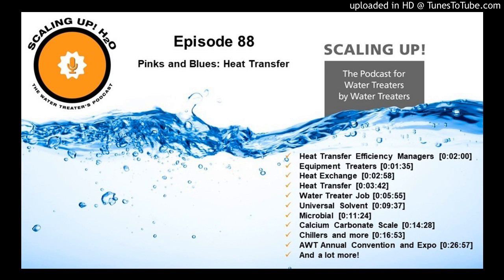So you know now, as a Scaling Up Nation member, that the thickness of a sheet of paper of scale is going to increase that chiller usage by 10%. Isn't that amazing? That small amount of scale increases the usage of energy by 10%. So now let's take an average chiller: a 500-ton chiller running 24 hours a day, 365 days a year, using 0.6 kilowatts per ton, and this customer is paying 7 cents per kilowatt.